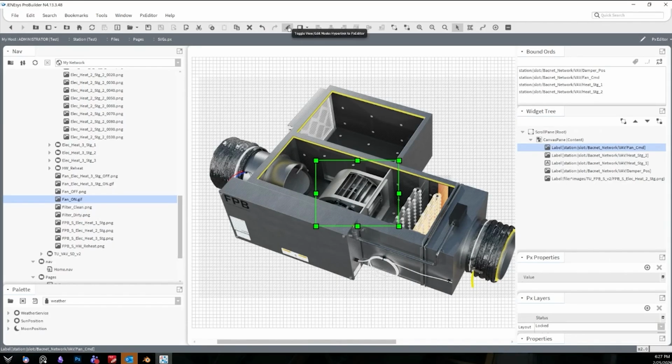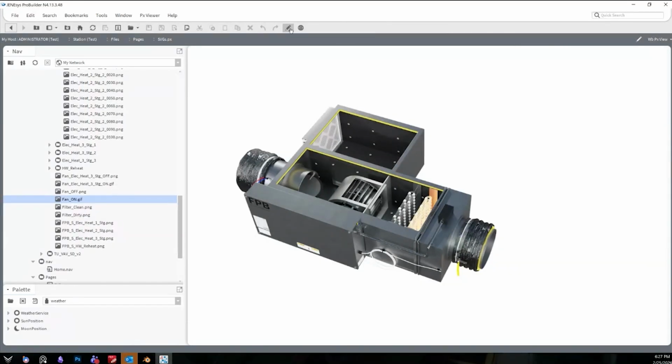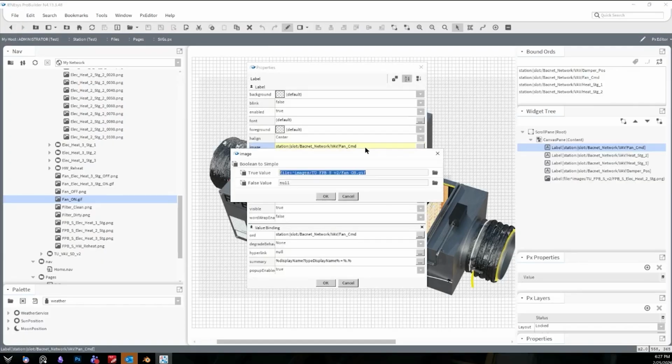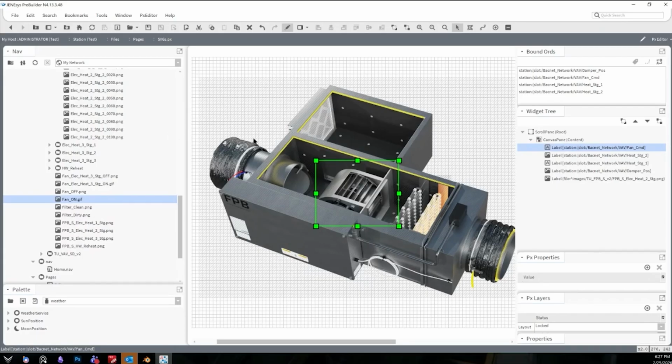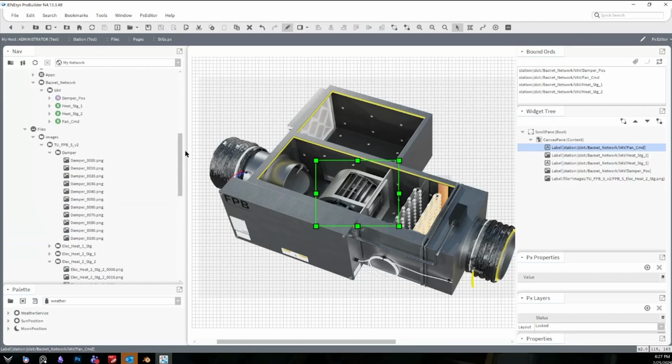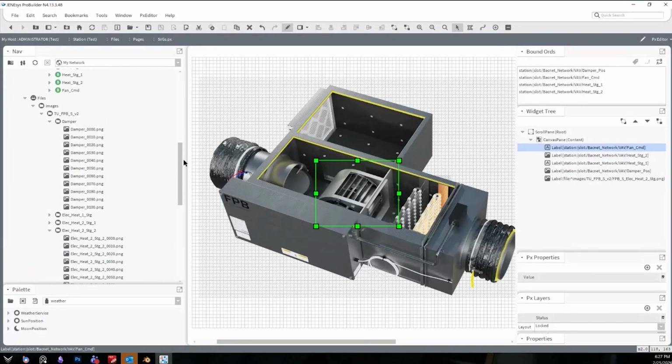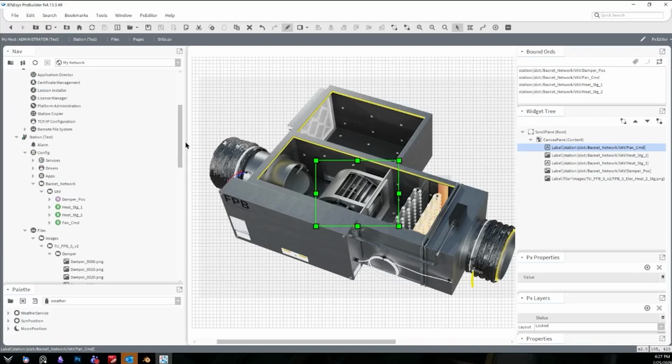I think I have a dirty filter. Yeah, I do, but they typically don't. Actually, filter. There you go. Filter status off of the VAV. What you could do is go ahead and create a maintenance schedule, and if the maintenance schedule is change your filters, right? Because they're supposed to change them in the fall, every year. I don't know how many times I've crawled up in there and found that thing sucked up into the, well, this is a series fan powered box, so yeah. Found that thing sucked up into there.